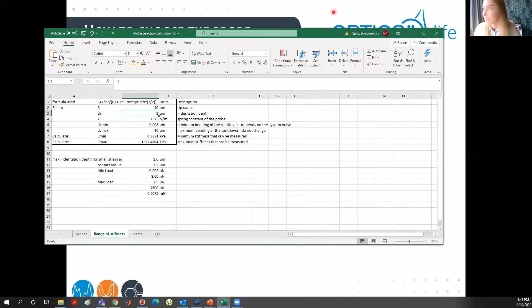So for example, you can now play around. Let's say you have a sample which is 250 kilopascals, and you are not sure if you can really measure it with the probe. You can very quickly check. For example, if I change the indentation depth to 1 micrometer, my range of what I can measure increases a lot. At smaller depths, I can measure many more stiffness values. You can also see how this changes if I change the tip size. If I use a smaller tip, then I can measure even more because there's more stress applied in the same area. I find this very handy, and before doing any measurements, I usually play around and see what can be done, which tip sizes I can use, which stiffness, and so on. So I recommend using it.